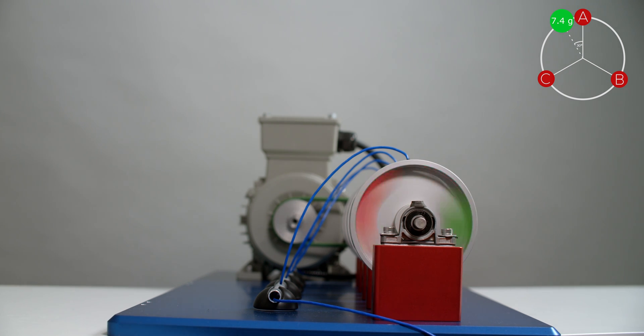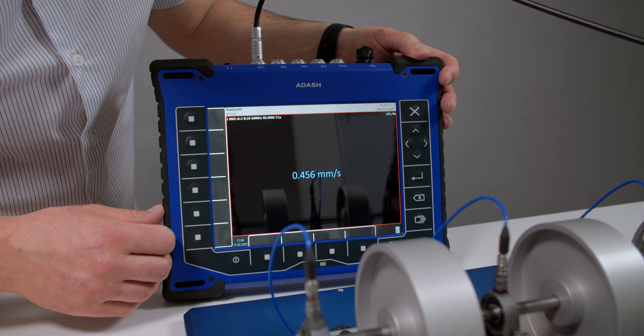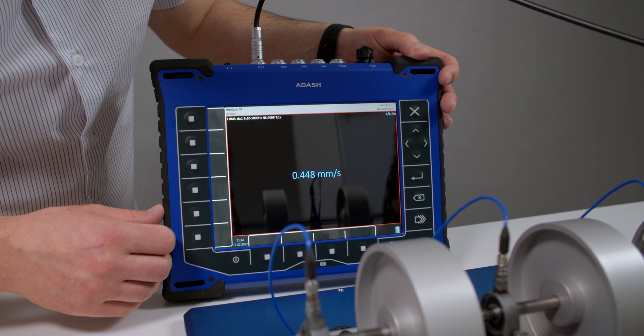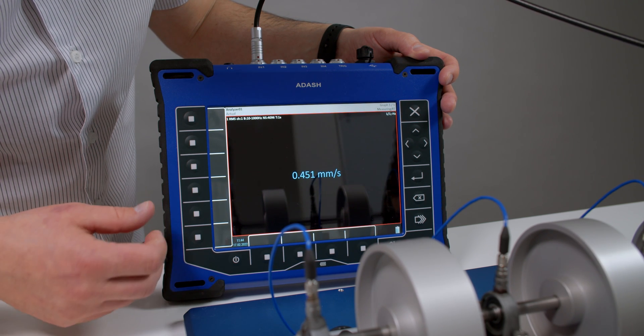Curious to see the residual vibration. Vibrations dropped from 2 millimeters per second to 0.45 millimeters per second. There is no bad result with using phone to balance the rotor, right?